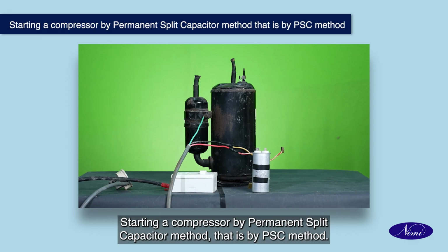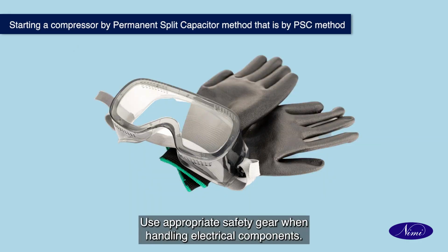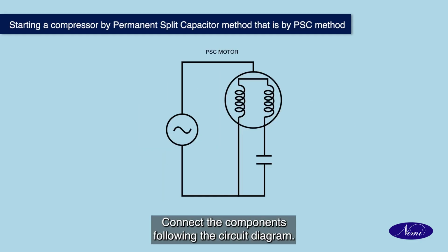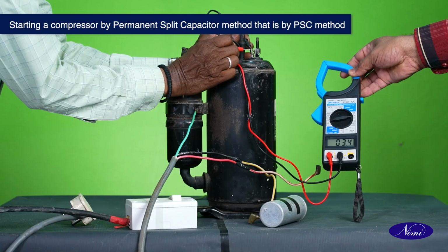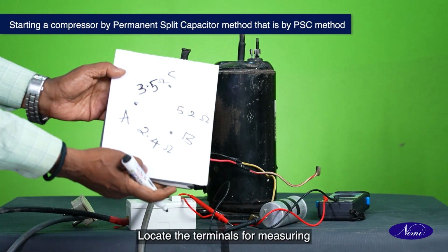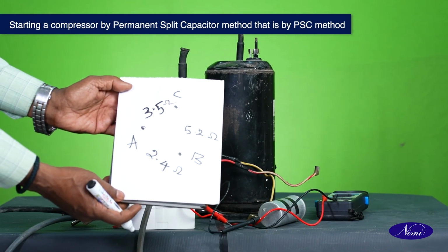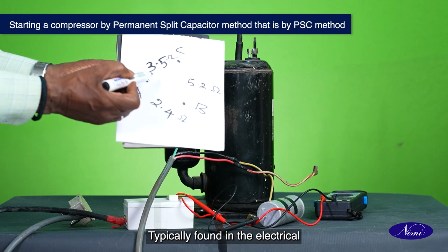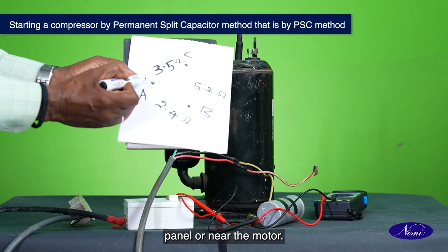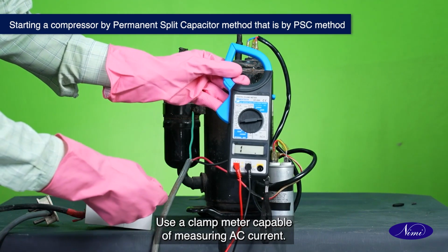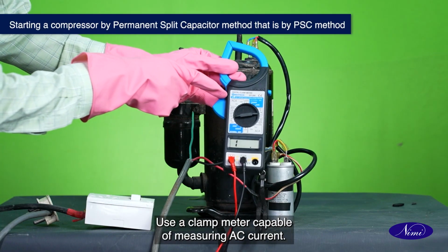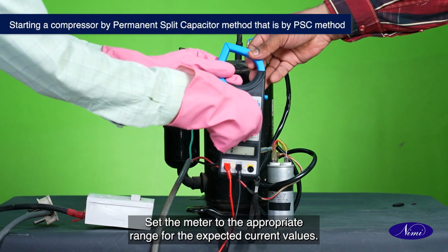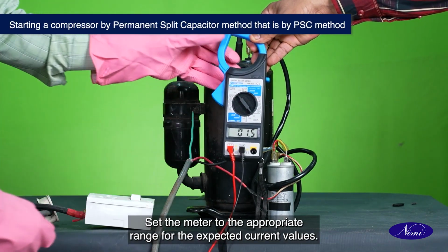Starting a compressor by permanent split capacitor method, that is by PSC method. Use appropriate safety gear when handling electrical components. Connect the components following the circuit diagram. Verify the wiring connections. Locate the terminals for measuring starting and running currents, typically found in the electrical panel or near the motor. Use a clamp meter capable of measuring AC current. Set the meter to the appropriate range for the expected current values.